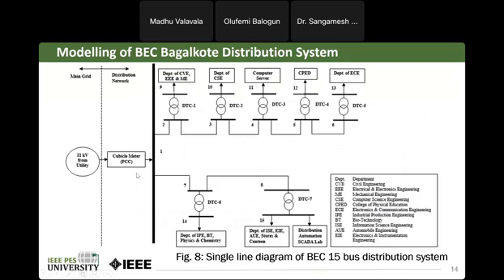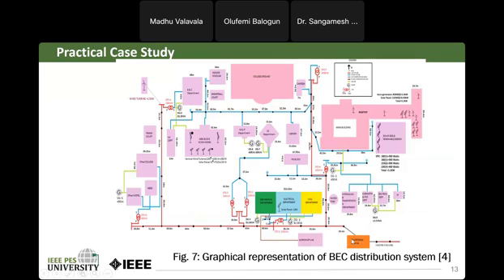That is whatever we have seen in that earlier diagram, so we are able to make it here. The bus numbers we are calling: bus number 1 will be the main one receiving at the cubicle meter, and the remaining buses are called bus 2 and bus 3, that is HT and LT buses. The HT is the main bus of the transformer and LT is the secondary of the transformer. So the HT bus we are calling the higher bus system, and LT is the low tension side bus system.